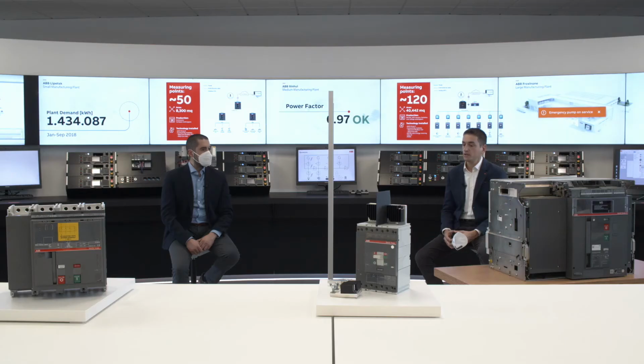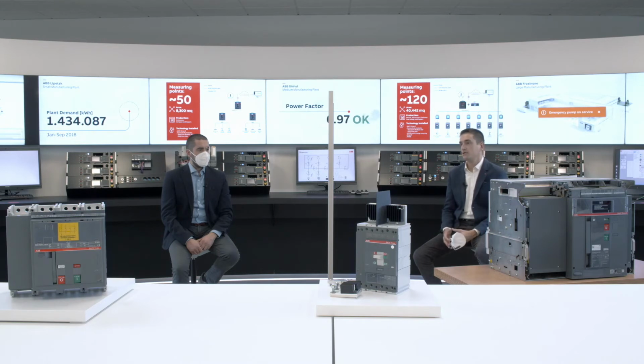To make it, we can also consider building the series connection manually, or use some of the solutions we provide as a manufacturer, and we also suggest. We are talking about jumpers, so shorting bus bars or shorting links that we always provide with every single frame and every single breaker. For all the different network configurations we may have, we have different and specific solutions. So we recommend having a look at our documentation to pick the best choice for each frame and for each network. Jumpers give many advantages. For instance, they are already provided in the right shape and with the right size to connect poles in series. So jumpers are the best solution to provide a quick and easy installation.